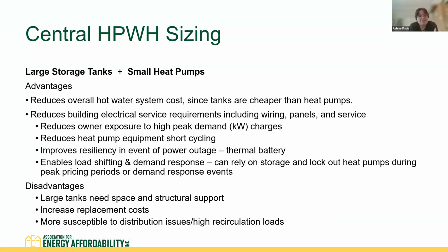Next slide. Like I already mentioned, when you're sizing central heat pump water heaters, we're typically looking at large primary storage capacity and small primary heating capacity as compared to a gas system. Designing a central heat pump water heater that way reduces overall hot water system cost, right? You could put in a system that's sized like a gas boiler and has huge primary heating and a small storage tank, but it's going to be expensive. We're going to require a lot of electrical capacity.